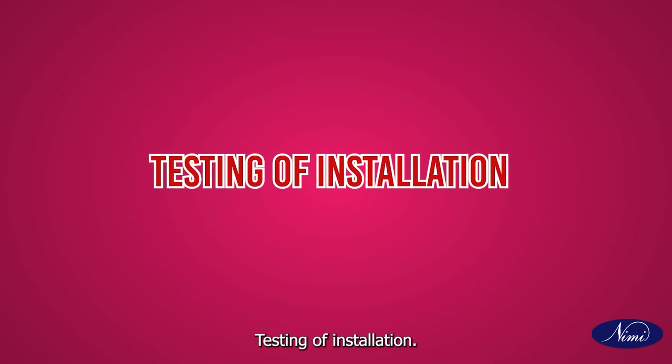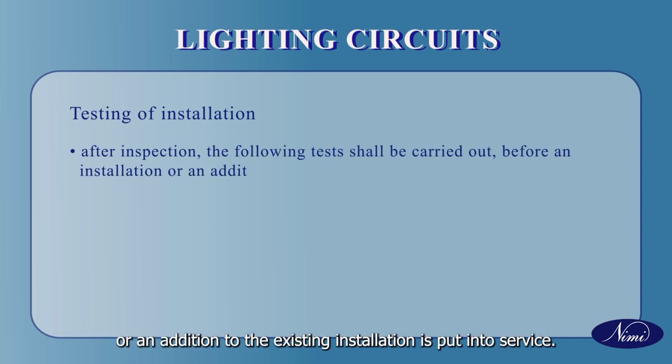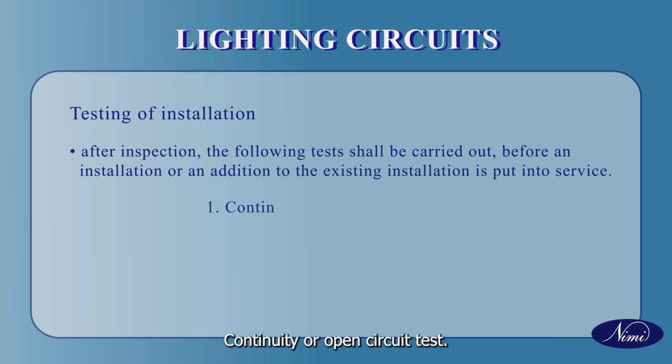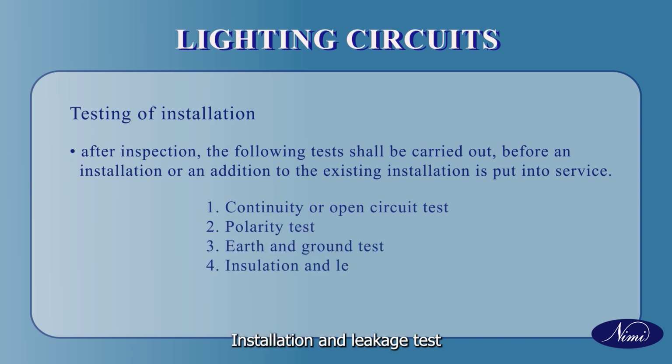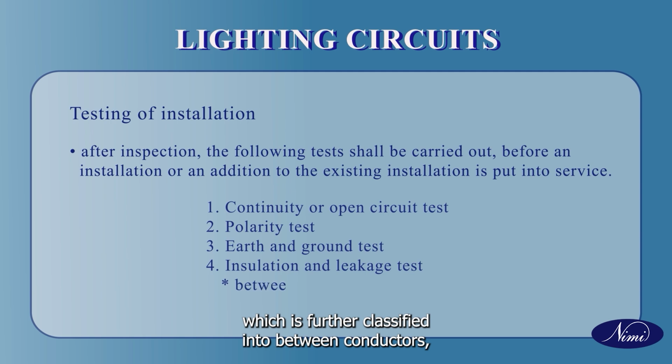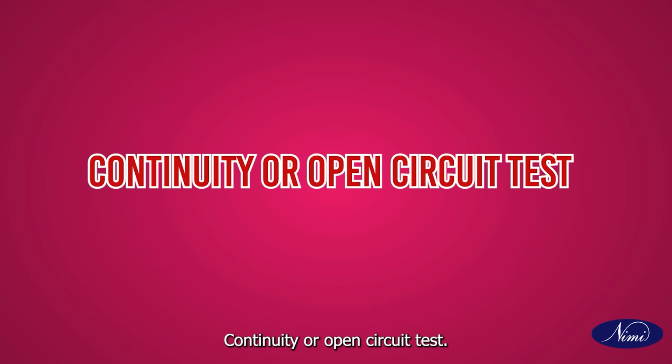Testing of installation. After inspection, the following tests shall be carried out before an installation or an addition to the existing installation is put into service: continuity or open circuit test, polarity test, earth and ground test, and insulation and leakage test, which is further classified into between conductors and earth.